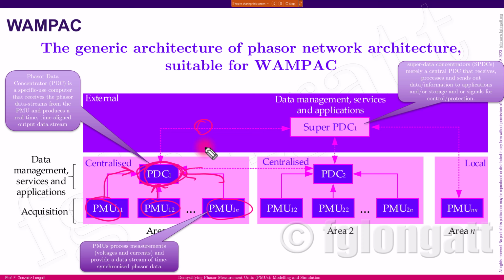The super data concentrator is basically a centralized, specific computer that we can use for processing all those data streams, but also for storage or to run applications. For instance, if those PMUs are receiving signals for frequency in different locations, we can send a vector of those frequencies to this data concentrator. We can run a wide area under-frequency load shedding scheme here, because we can concentrate all those signals, and if an event happens, we can send trip signals to the devices. So the super data concentrator is more than a computer; inside it we can run applications using the data stream coming from the phasor measurement units.